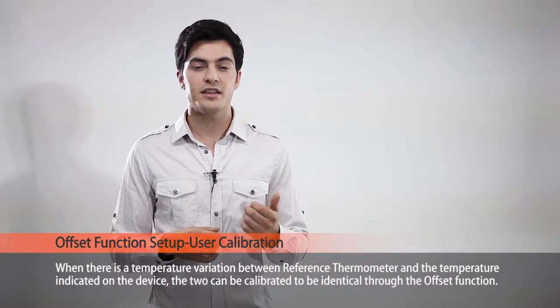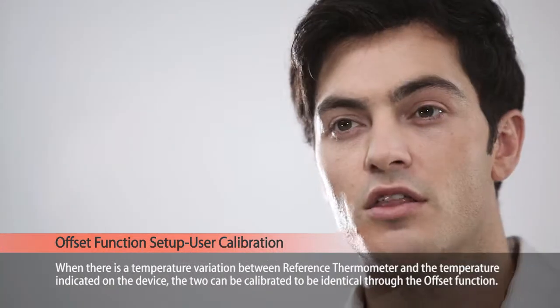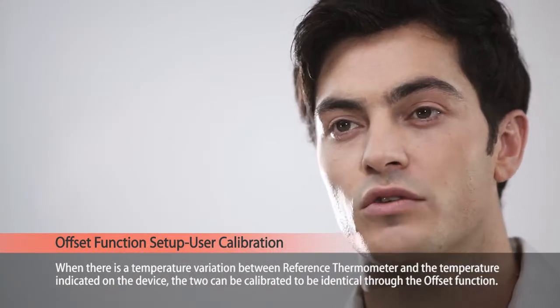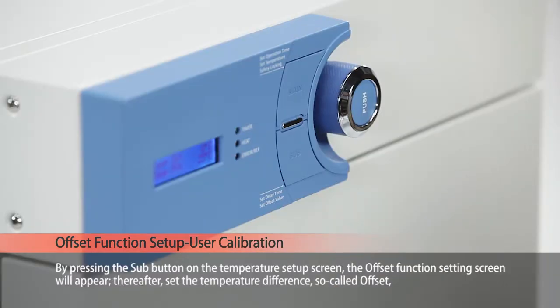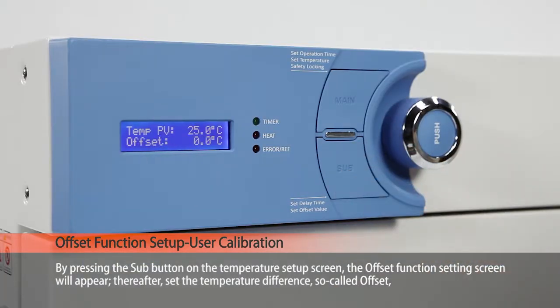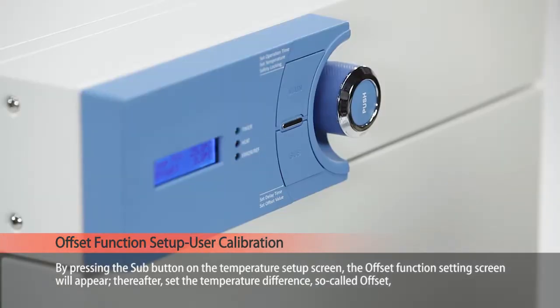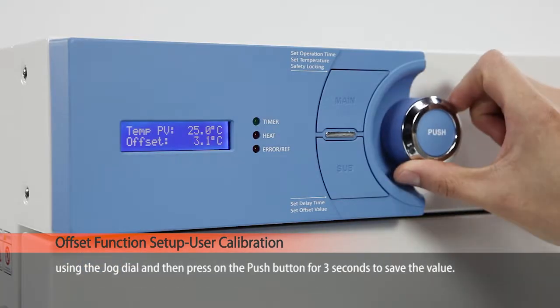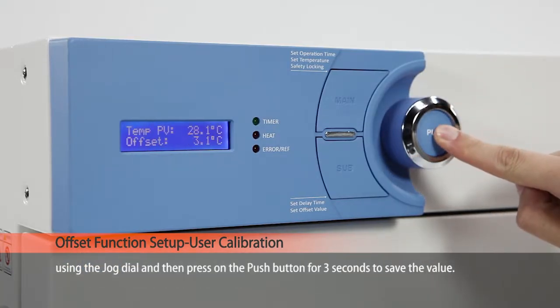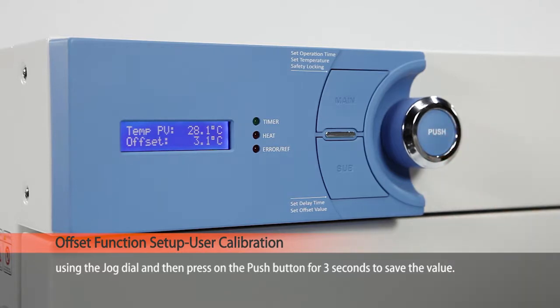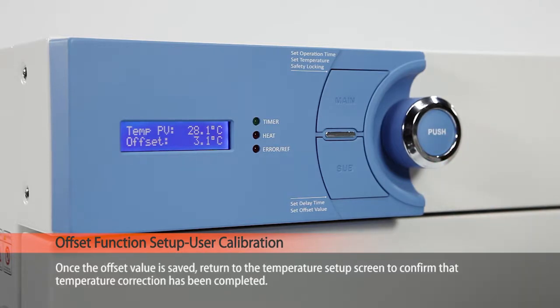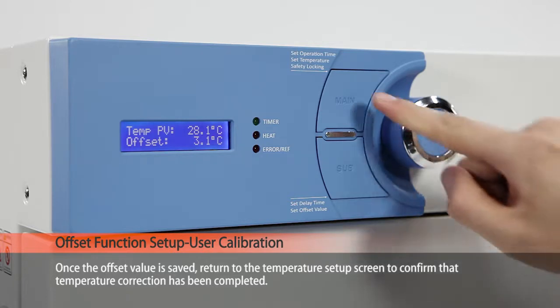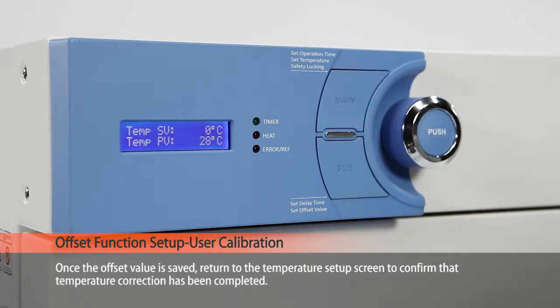When there is a temperature variation between reference thermometer and the temperature indicated on the device, the two can be calibrated to be identical through the offset function. By pressing the sub button on the temperature setup screen, the offset function setting screen will appear. Thereafter, set the temperature difference, so-called offset, using the jog dial, and then press on the push button for 3 seconds to save the value. Once the offset value is saved, return to the temperature setup screen to confirm that the temperature correction has been completed.